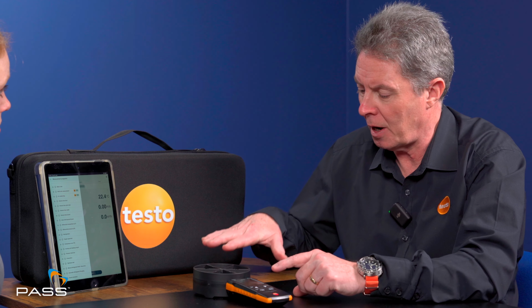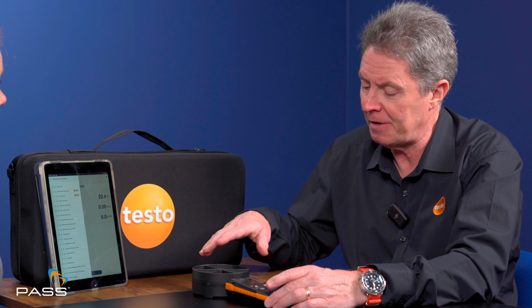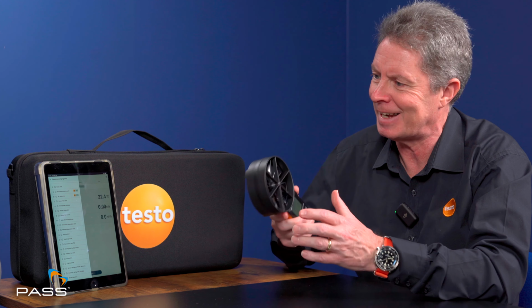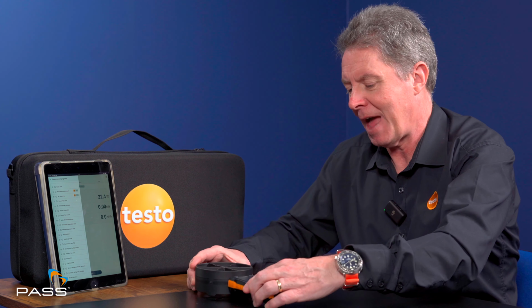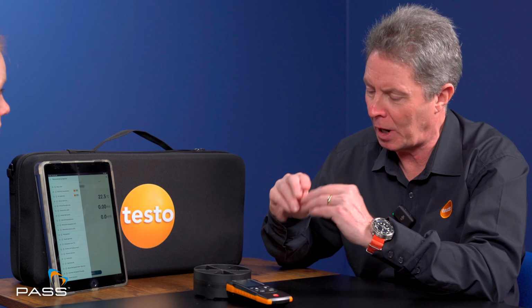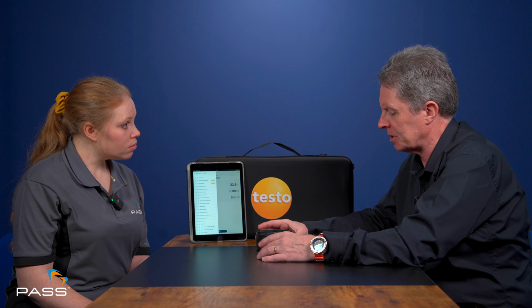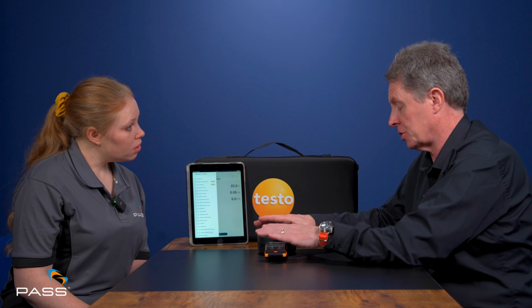There are also other anemometers in that range. If you're measuring airflow not at a grill or vent but within ductwork, you wouldn't use an anemometer like this because you can't physically get into ductwork. So you'd have something like the Testo 425 or 416, an anemometer designed to go inside ductwork, much smaller, enabling you to take those measurements. The Compact Class, this being just one of them, is a really flexible range of products.